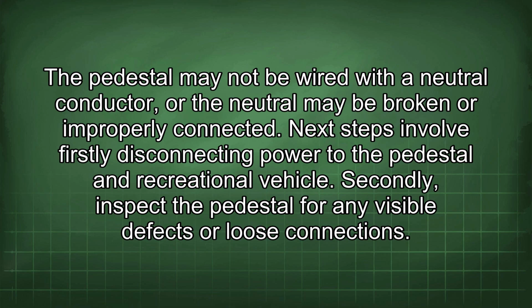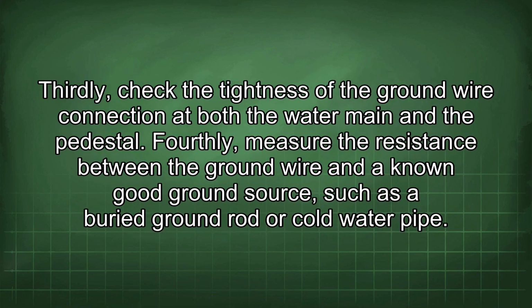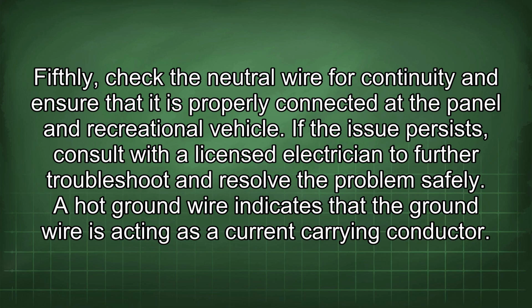Next steps involve, firstly, disconnecting power to the pedestal and recreational vehicle. Secondly, inspect the pedestal for any visible defects or loose connections. Thirdly, check the tightness of the ground wire connection at both the water main and the pedestal. Fourthly, measure the resistance between the ground wire and a known good ground source, such as a buried ground rod or cold water pipe. Fifthly, check the neutral wire for continuity and ensure that it is properly connected at the panel and recreational vehicle.